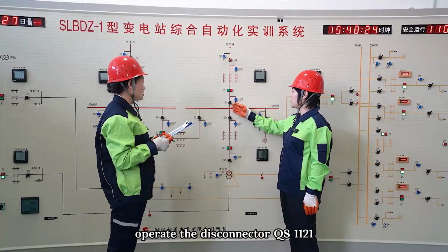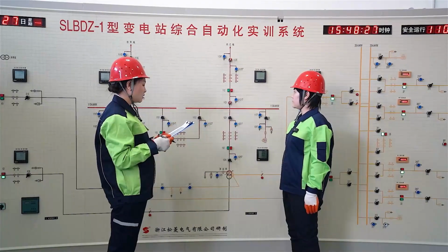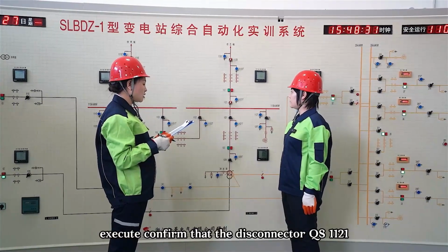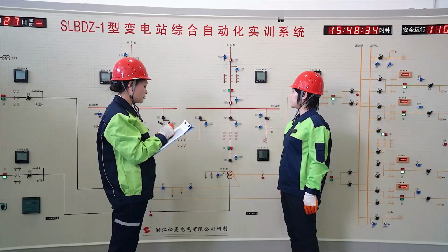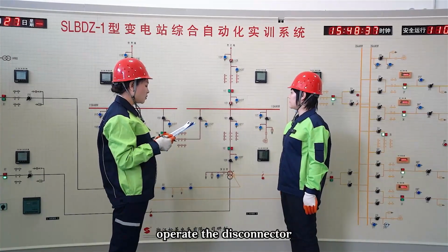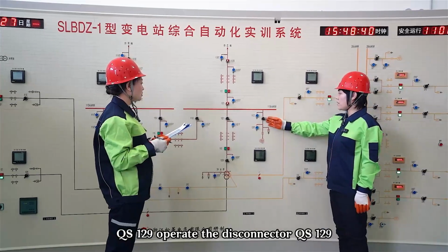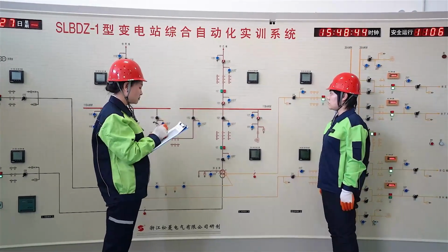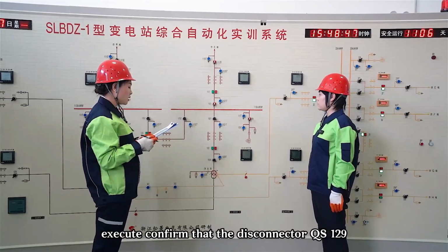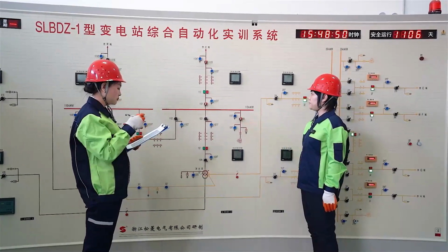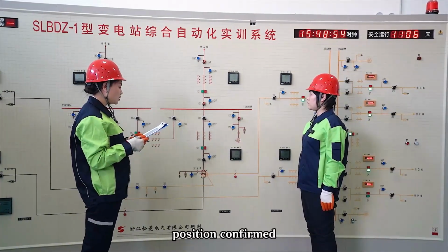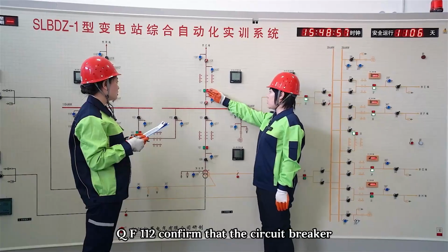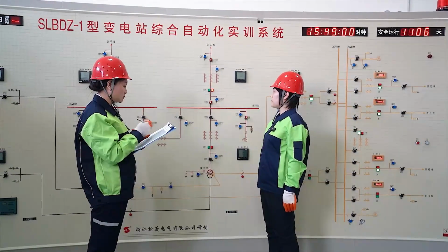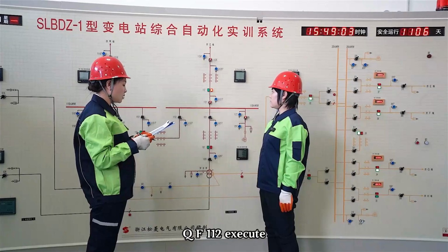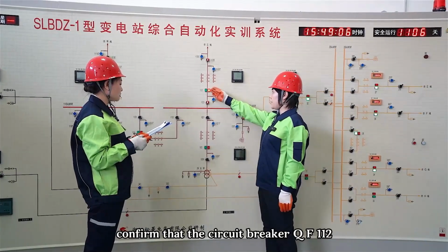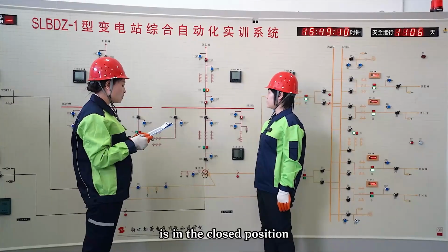Operate the disconnector QS 1121. Execute. Confirm that the disconnector QS 1121 is in the closed position. Confirm. Operate the disconnector QS 129. Execute. Confirm that the disconnector QS 129 is in the closed position. Confirmed. Close the circuit breaker QF112. Execute. Confirm that the circuit breaker QF112 is in the closed position.